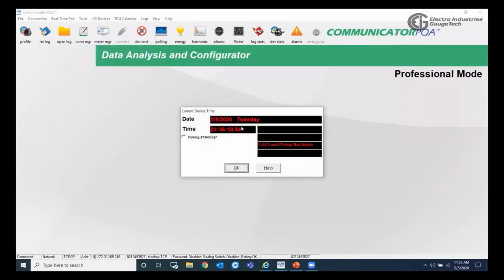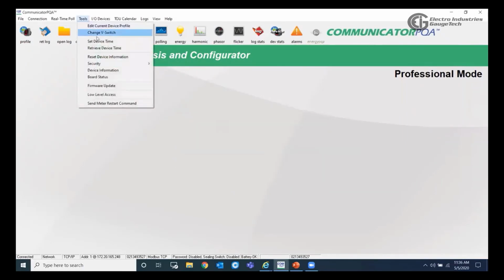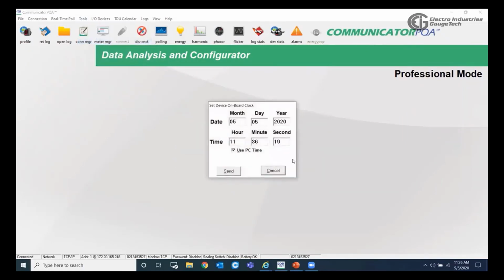Also in tools, we can go to retrieve the device time from here. And if the device time or the date is not correct, we can go to tools again and set device time. All you have to do is make sure that the time in your PC is correct, use the PC time and hit send, and that will send the date and the time to the meter.